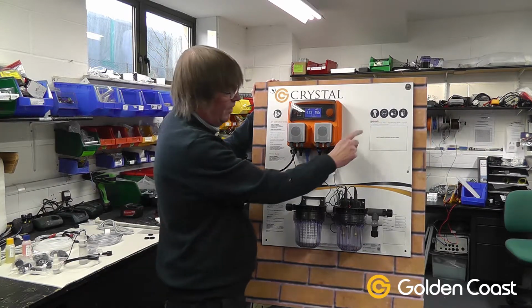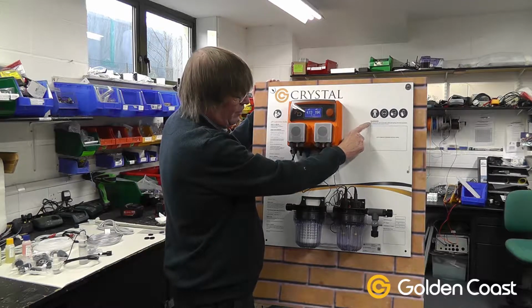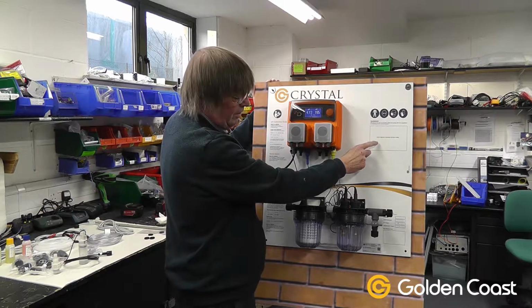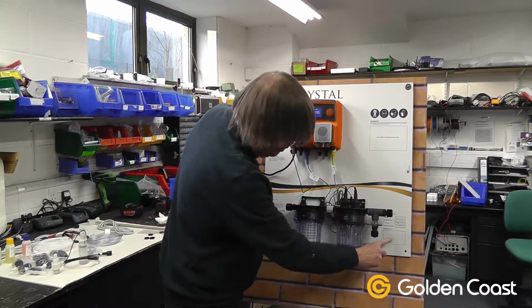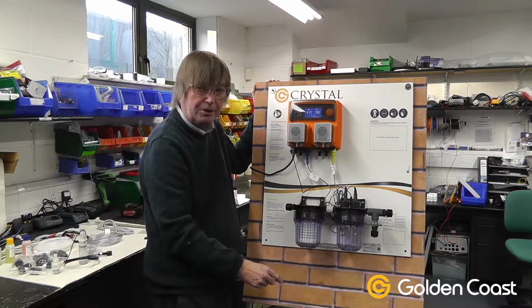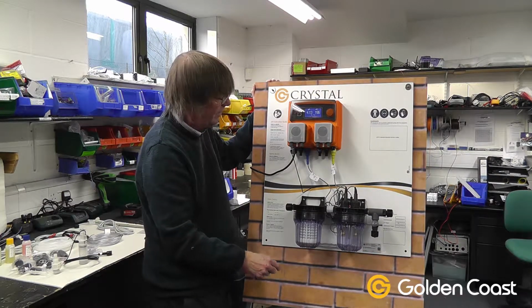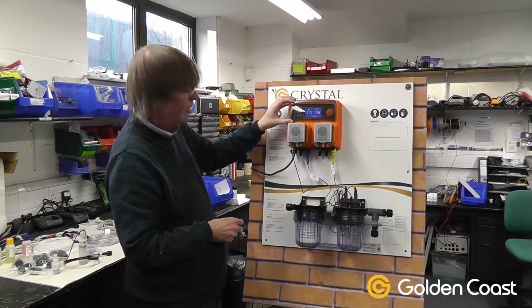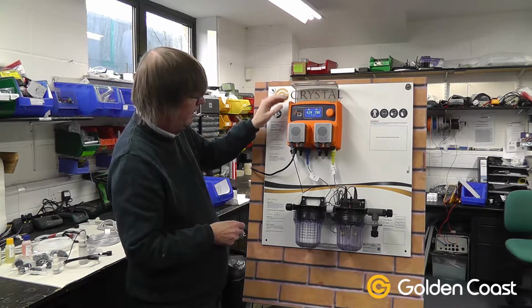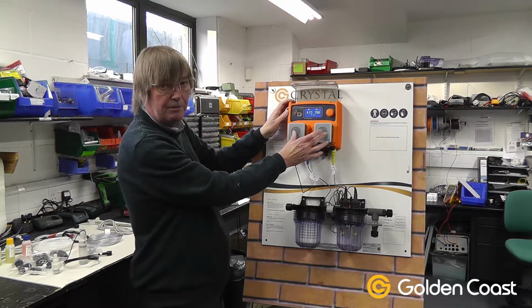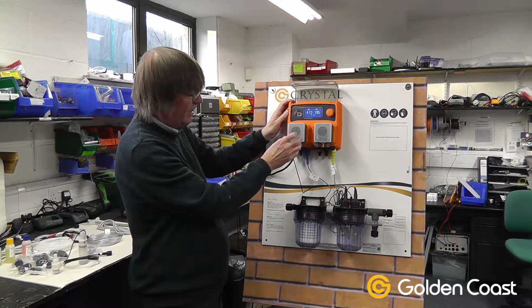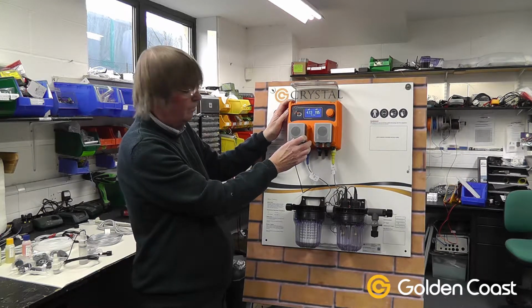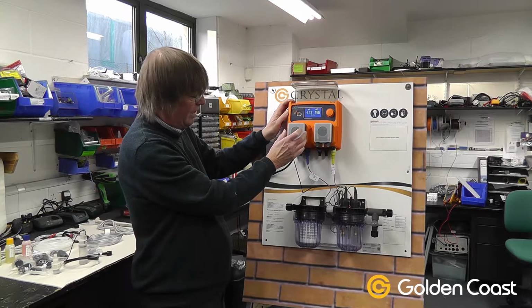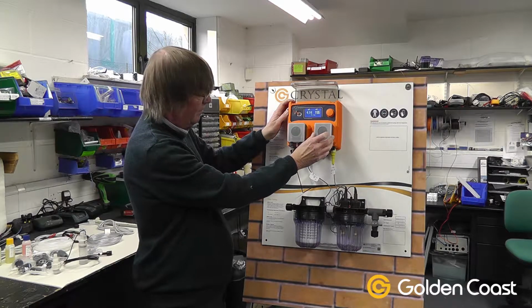The other side of the board has some health and safety information, a place to put a sticker for whoever fitted the board, and then the very bottom for when it was installed and commissioned and signed for and dated properly. This particular controller is one of the WD ones again, and has two peristaltic pumps on the front. And these can be set to run either on, off or proportional modes. One for the pH correction and one for the sanitizer.